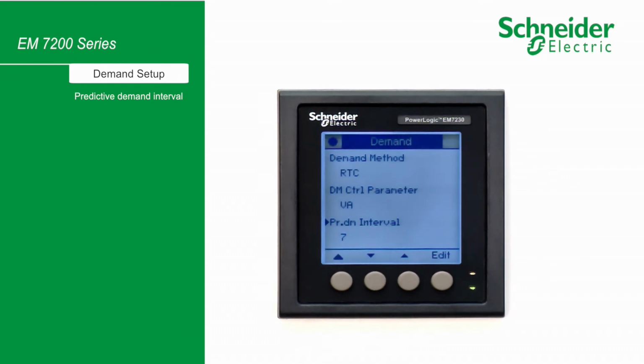Prediction demand interval could be 4 to 7 minutes if the demand interval is 15 minutes, and when the demand cycle is set for 30 minutes, the prediction demand could be 7 to 15 minutes. Prediction demand interval can be set from 1 to 30 minutes. Let's select 7 minutes. Then press OK.